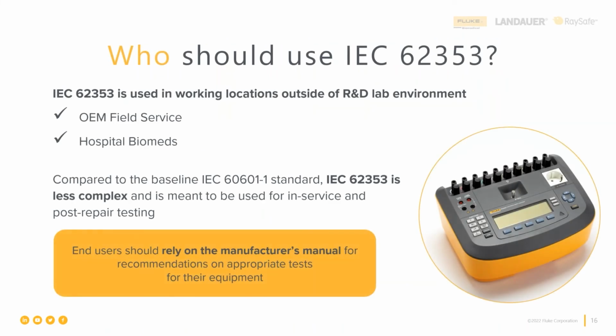All right, so what about this other standard, IEC 62353? The IEC 62353 is used either during or after the acceptance testing. In other words, when we receive the unit, it's perfectly appropriate for us to use one of the 3 testing methods described in IEC 62353. So it's appropriate for use by the medical device manufacturer field service or any third-party provider that is providing field service engineers to client sites. Also, for all of us that are hospital-based biomeds, IEC 62353 is very appropriate.